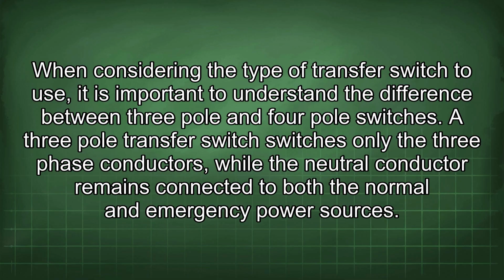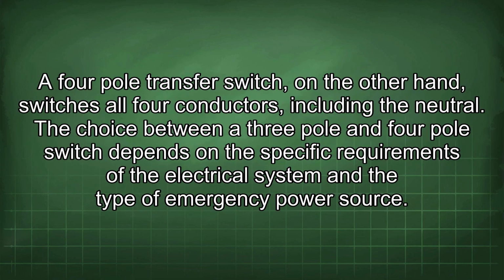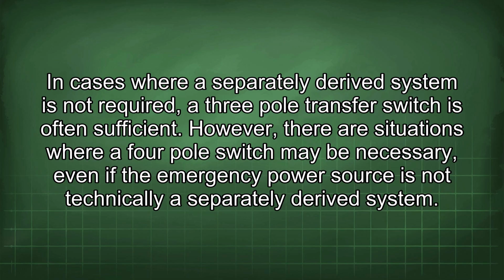When considering the type of transfer switch to use, it is important to understand the difference between 3-pole and 4-pole switches. A 3-pole transfer switch switches only the 3-phase conductors, while the neutral conductor remains connected to both the normal and emergency power sources. A 4-pole transfer switch, on the other hand, switches all 4 conductors, including the neutral. The choice between a 3-pole and 4-pole switch depends on the specific requirements of the electrical system and the type of emergency power source. In cases where a separately derived system is not required, a 3-pole transfer switch is often sufficient. However, there are situations where a 4-pole switch may be necessary, even if the emergency power source is not technically a separately derived system.